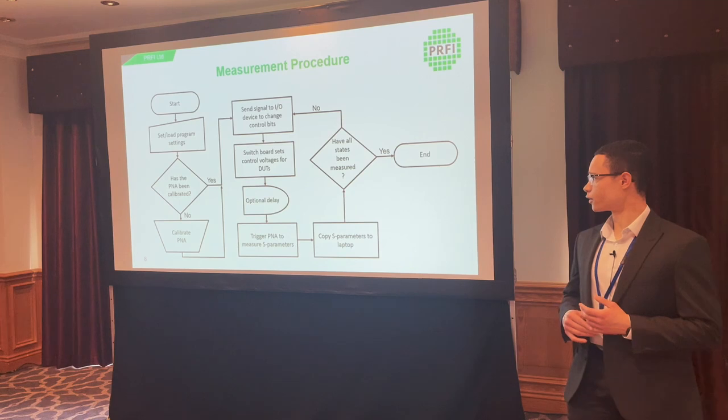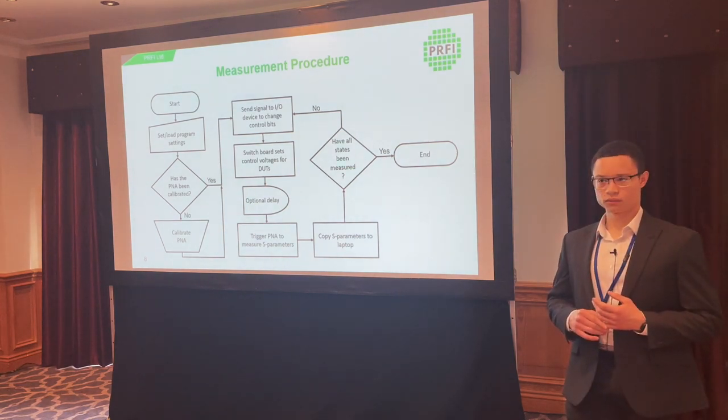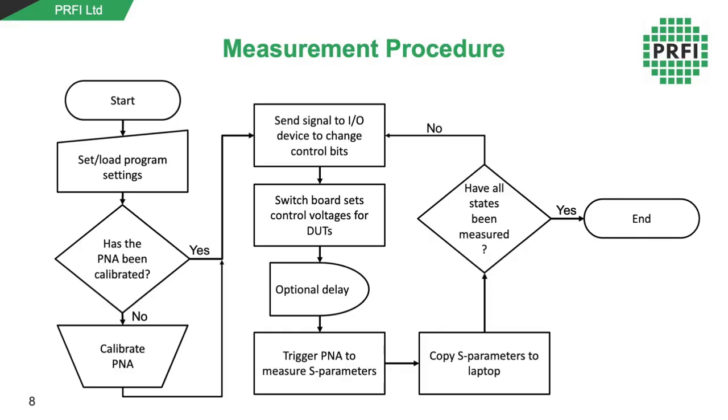This is a flowchart showing the main measurement procedure the program goes through. It starts by connecting to the instruments, then we either set or load the program settings — these get saved automatically at the end so you can reload them from a previous run. If the PNA has been calibrated, it proceeds to the main automation loop; if not, it gets calibrated with the ECal module, done manually.